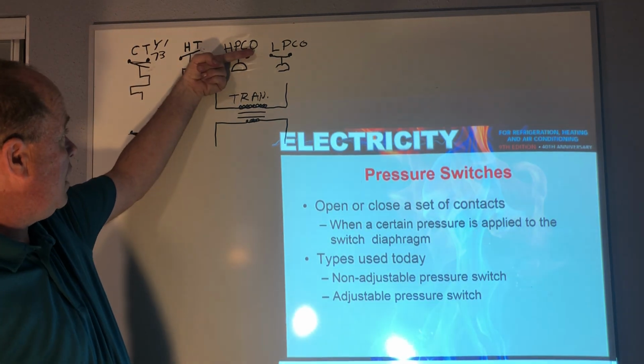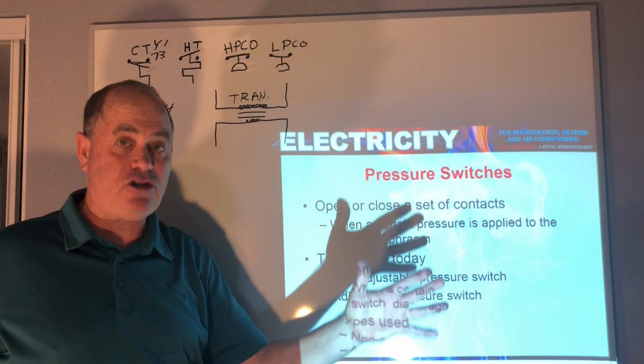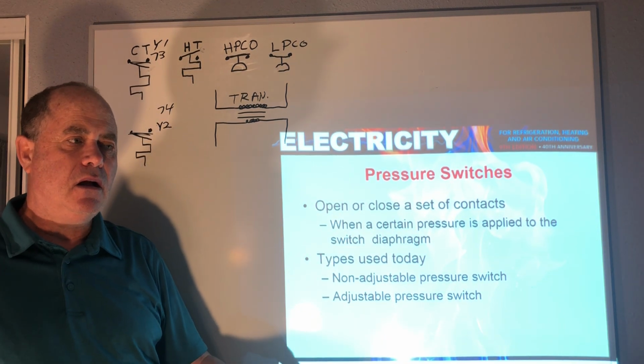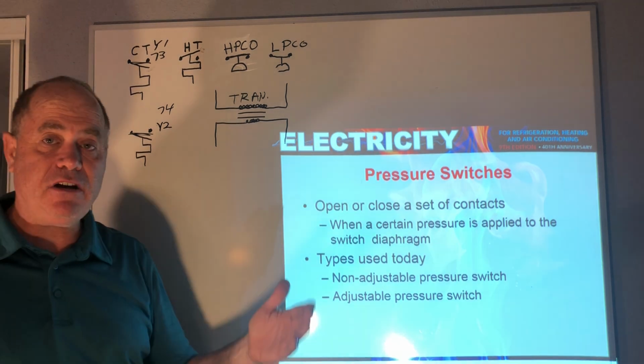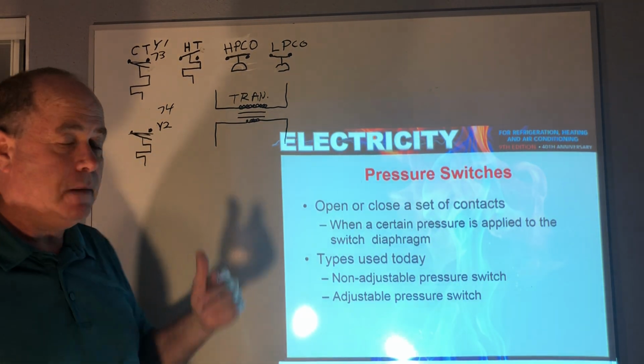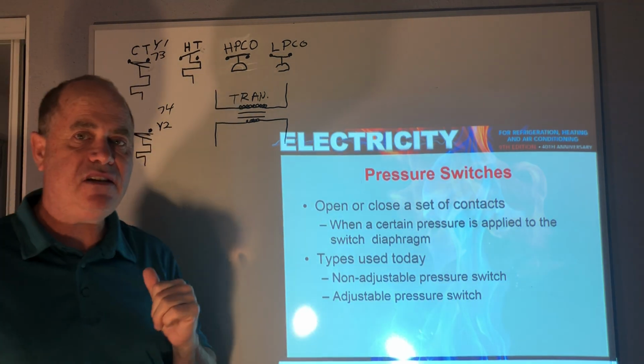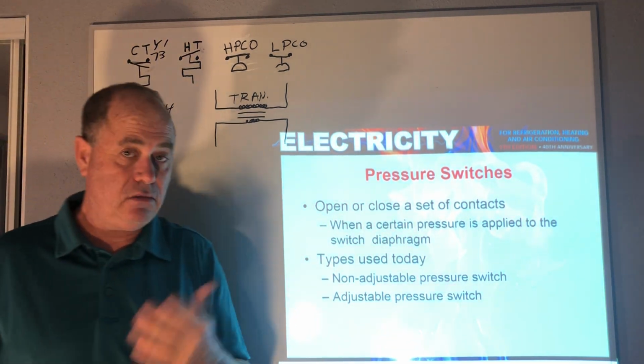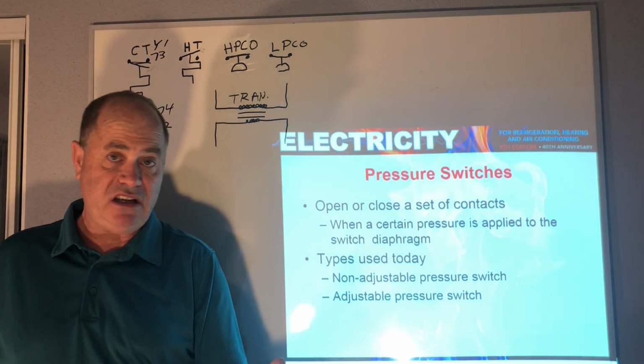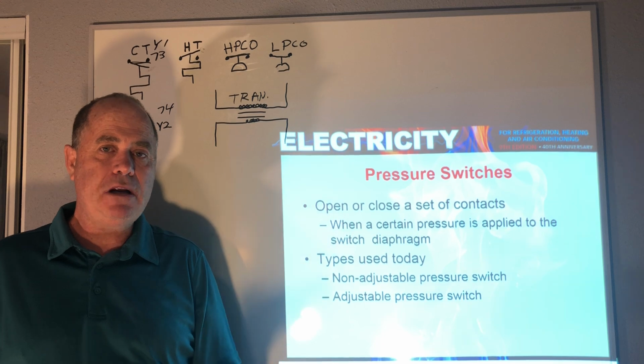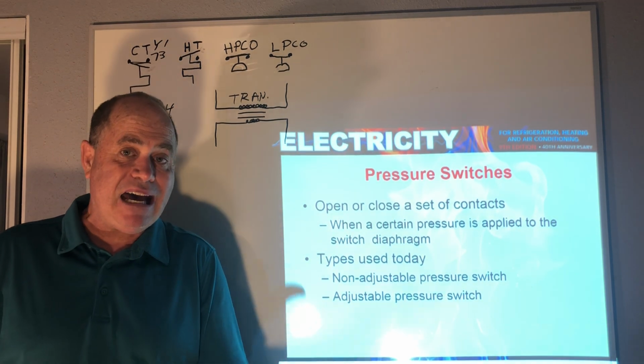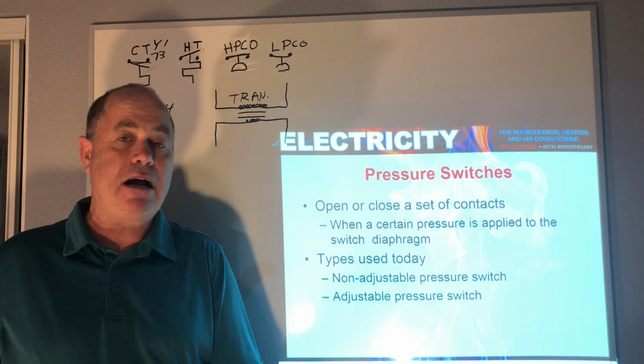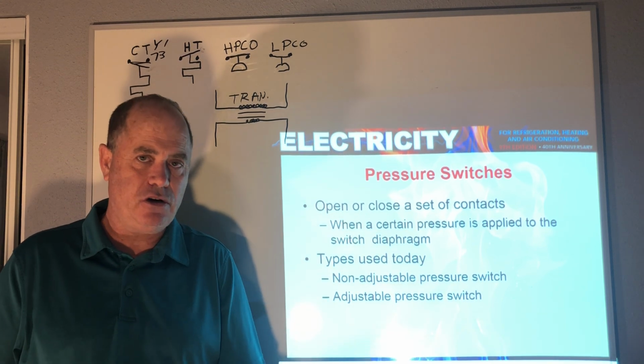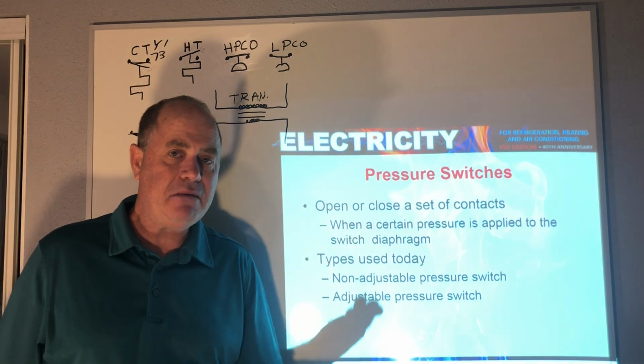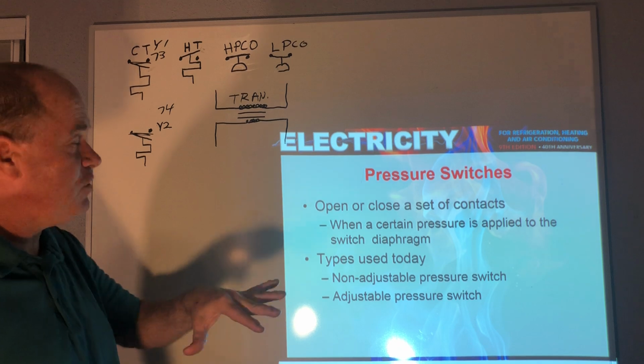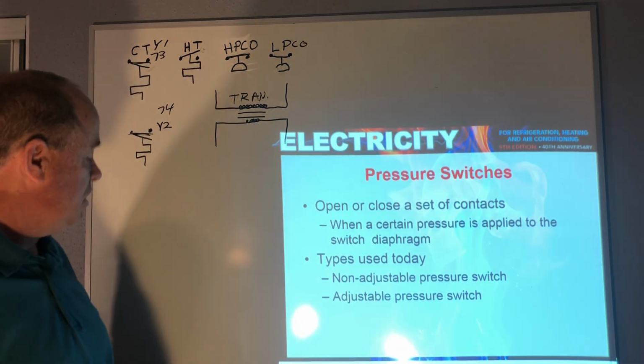Similarly, the high pressure cutout would open up if the pressure on the high side got too high, and to protect the compressor and the system from failure, it will open up as a safety. And the most common reason that a high pressure cutout is going to be activated, open up, is a dirty condenser. Dirty condenser all day long will cause it to open up. The second most common reason would be a bad condenser fan motor, or a condenser fan motor that's not running, perhaps because of a bad capacitor that serves that fan motor. So that would open up and save it. But there's other applications of pressure switches I want you to be aware of.